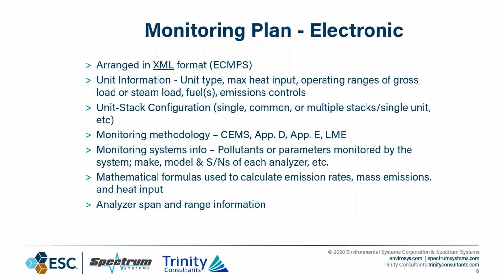The type of methodology that you use for monitoring, whether that is a full-on Acid Rain CEMS, Appendix D for your gas or gas and oil, Appendix E, or LME, which stands for low mass emission monitoring. The systems information itself, the components that you use for monitoring your pollutants, make, model, serial numbers of each analyzer, etc. The equations that you use to calculate your emission rates, your mass emissions, your heat input, etc. And your analyzer span and range information.